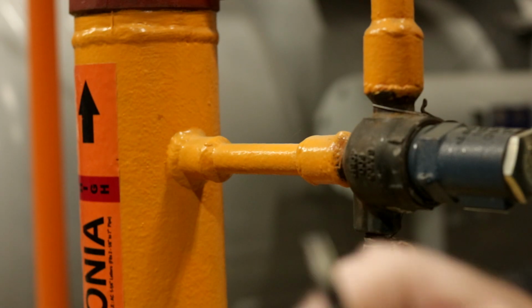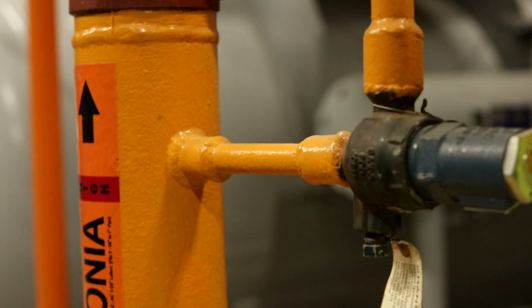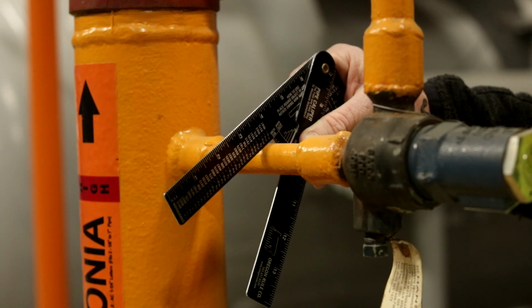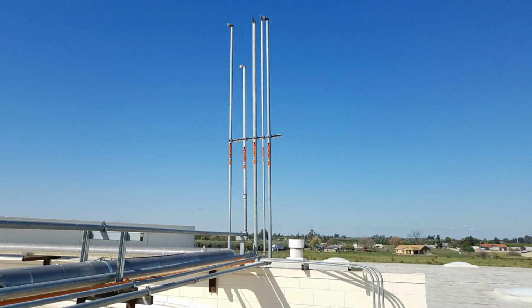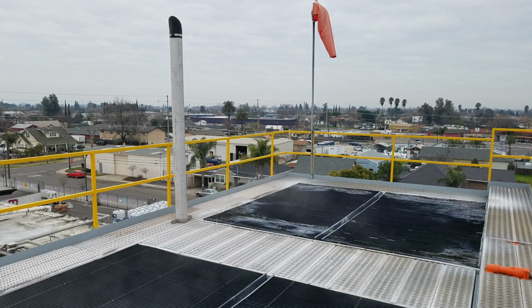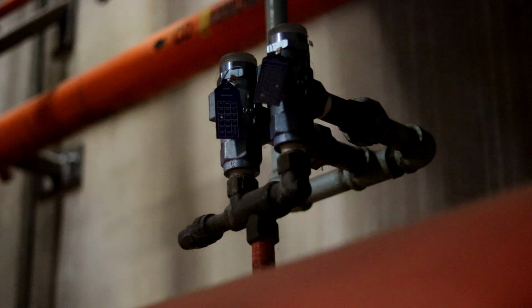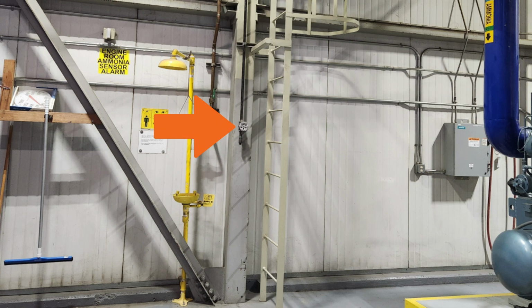The size of the discharge piping must be properly engineered to prevent excessive back pressure during a release, and termination of relief valves must be adequate. For ammonia, the termination pipe must not be within 20 feet of a building opening and must be 15 feet above grade or 7.25 feet above a roof or platform. Maintenance on relief valves consists of replacing the valves every 5 years and draining water from the discharge piping annually where that provision is provided.